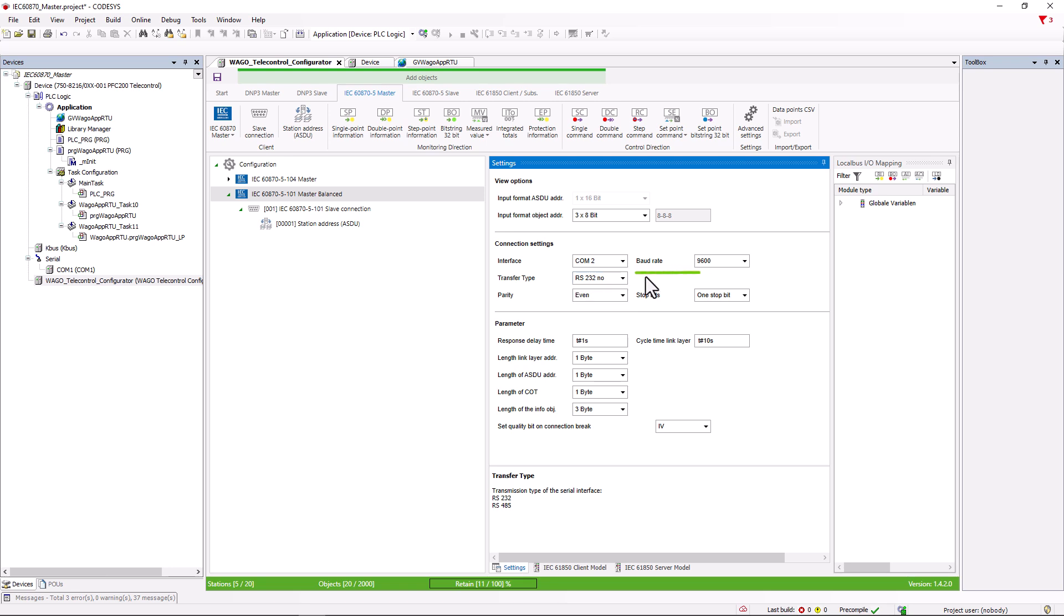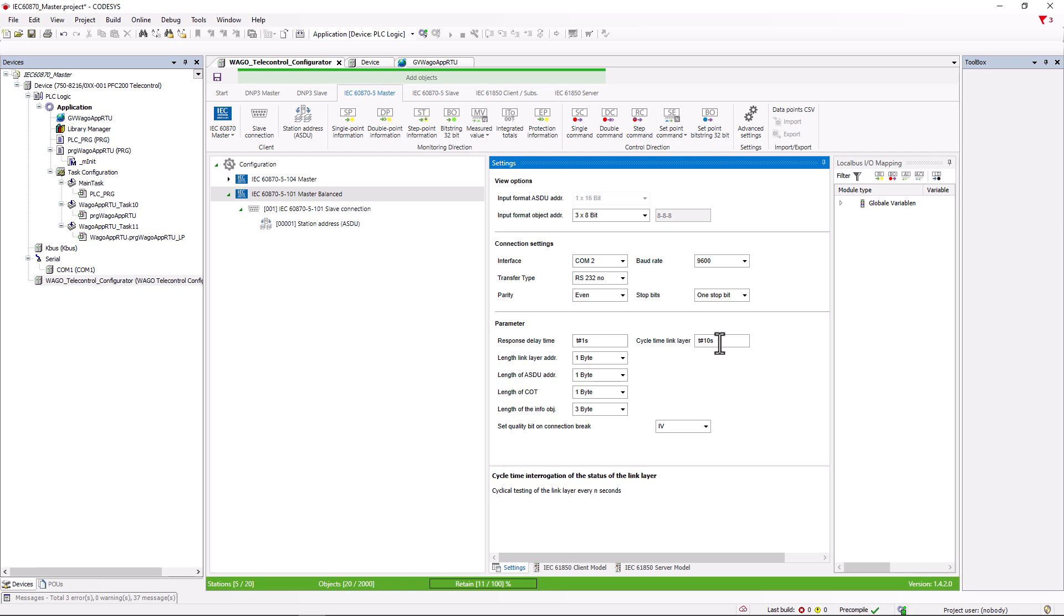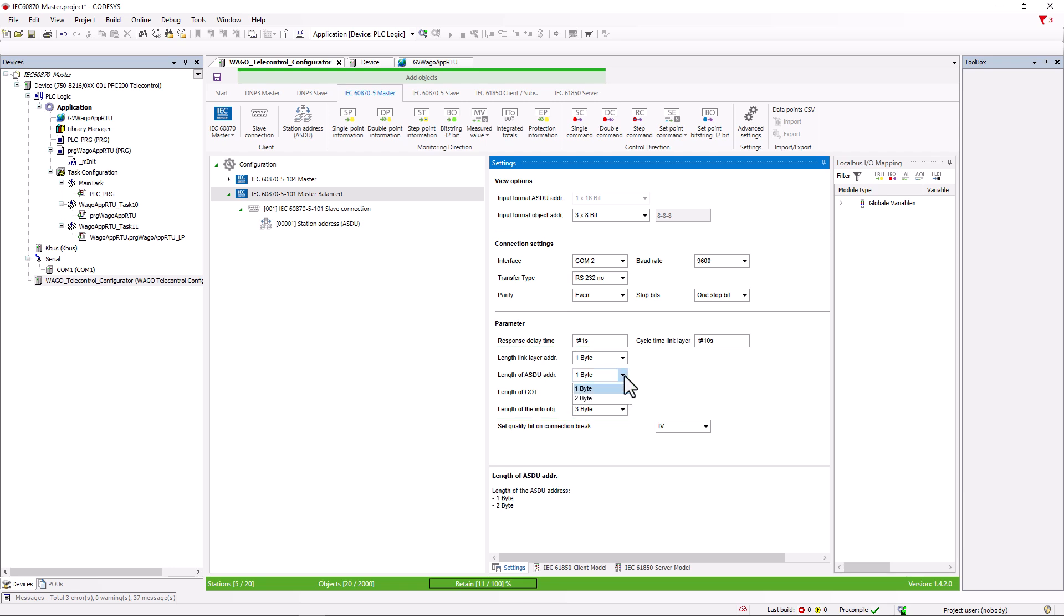Next are the Baud Rate, Parity and Stop bits. At the top are the View options. Compared to the Slave, the Response Delay Time and the Cycle Time link layer have been added to the parameters. The Response Delay Time is the time the Master waits for a response from the Slave. The Cycle Time link layer can be used to specify how often the test telegram should be sent to test the connection. And here how a telegram is structured, so how many bytes are used to represent the ASDU address, or whether the reason for the transmission is transmitted with the source address, in which case an additional byte is required or without. It is important that these parameters are set the same for Master and Slave. Otherwise the telegrams will have no meaningful content.